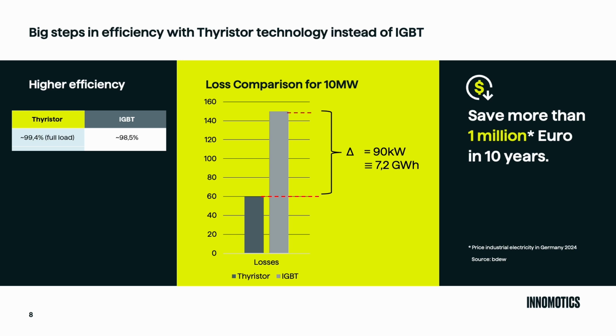What is interesting in the efficiency? We can build rectifiers with thyristor technology, and we can build them with IGBT technology. Thyristors typically have a better efficiency than IGBTs. Here we are announcing 99.4%, which has been tested. IGBTs have efficiencies in the total system of maybe 98, maybe 98.5, something like this, which is also good efficiency, but this roughly 1% needs to be calculated in the losses of the production. If we do that here on a 10 megawatt system, which we can see in the middle, it means we are having 90 kilowatt more losses. And these 90 kilowatt losses then need to be calculated in the electricity cost for the OPEX. We can calculate this 90 kilowatt with an operating time of maybe 8,000 hours in a year. For 10 years, we are talking about 1.2 million euros which you can save in the OPEX by using these high efficiency thyristors.